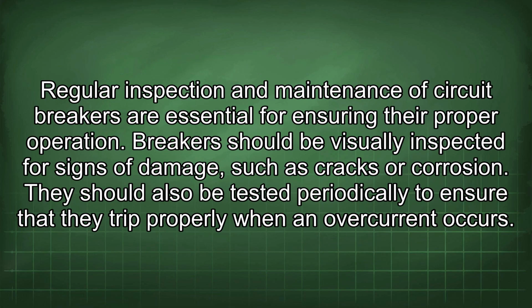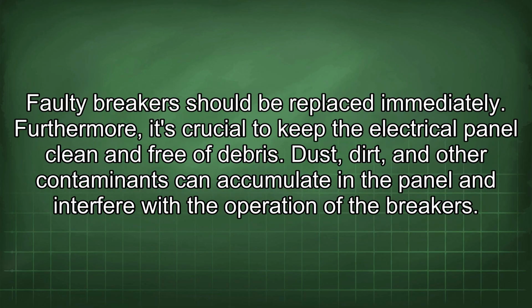Regular inspection and maintenance of circuit breakers are essential for ensuring their proper operation. Breakers should be visually inspected for signs of damage such as cracks or corrosion. They should also be tested periodically to ensure that they trip properly when an overcurrent occurs. Faulty breakers should be replaced immediately.